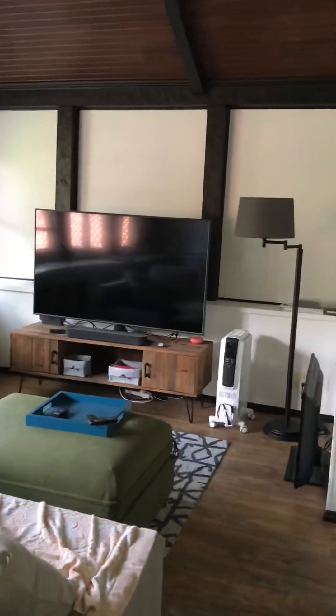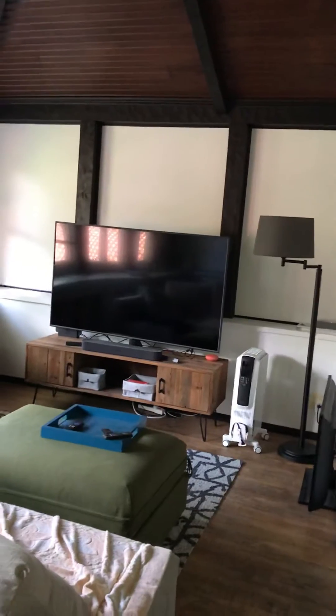About 600 square feet plus or minus — I'll drill down and have a look. We're probably looking at a 12,000–15,000 BTU unit.